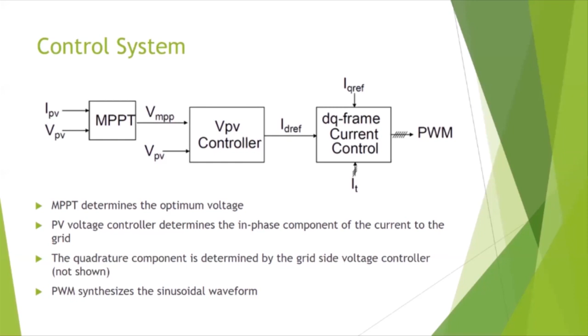Now the question is, when we talk about ID reference and IQ reference, ID is the in-phase component of the current. You have to synchronize this to the grid to determine the phase angle. So we can synchronize using a phase lock loop.